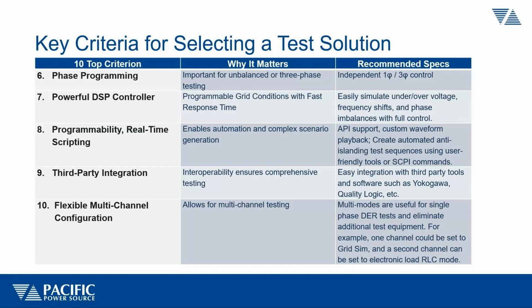Flexible multi-channel configuration is nice if you're dealing with single phase, split phase, and three phase DER testing. If you're a test lab, you want to be able to handle all kinds of DERs, preferably. So you want the ability to have different phase modes on your equipment. Those are all important criteria for the requirements of the equipment on the test setup.